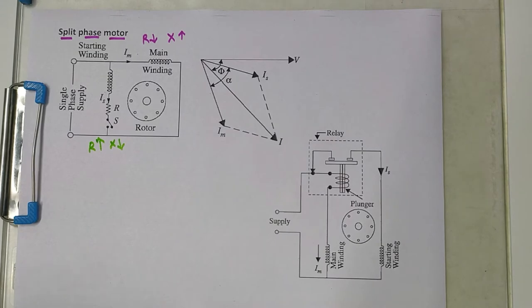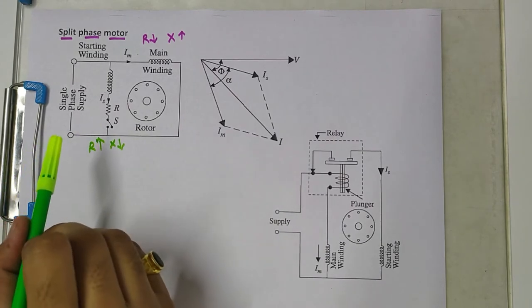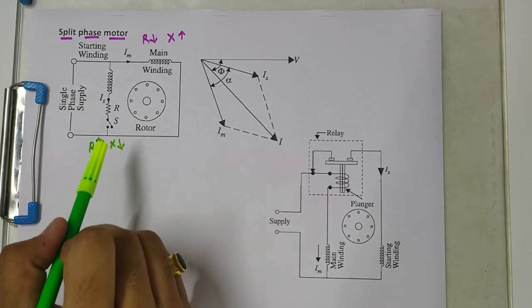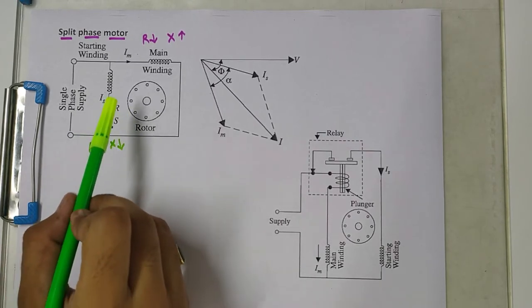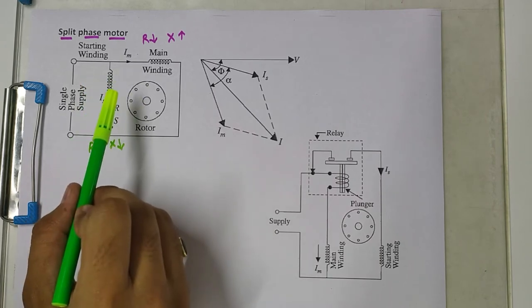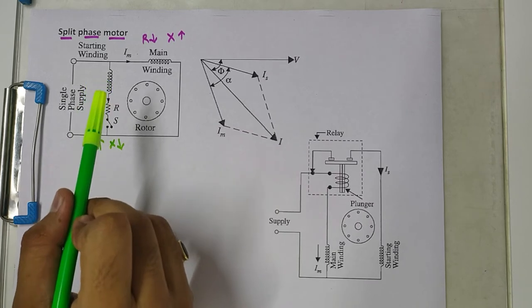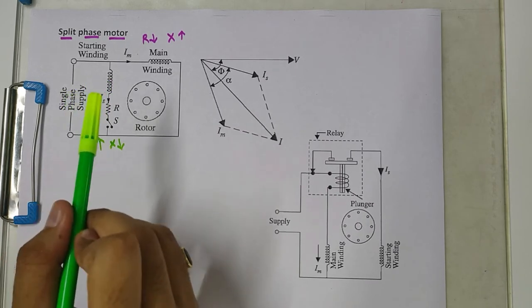The resistance of the starting winding can be increased by either connecting a high value resistance in series with it or by choosing a high resistance thin copper wire. Because as the cross section of the copper wire reduces, the resistance of the same will increase.